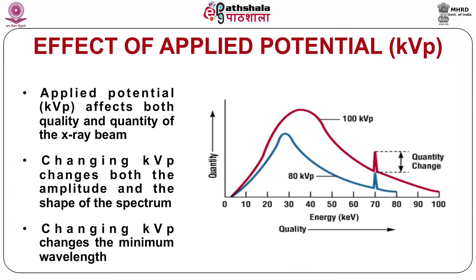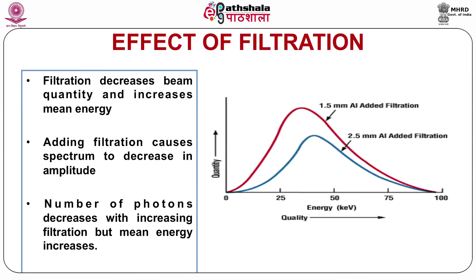Now the filtration. Filtration decreases beam quantity and increases mean energy and thereby quality of the X-ray beam. The addition of filter, that is absorbers or attenuators, causes the spectrum to decrease in amplitude and shift towards the higher energy side. The number of X-ray photons decreases with increasing filtration, but mean energy increases.